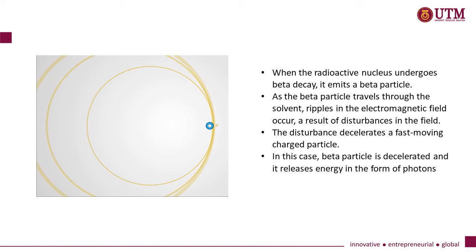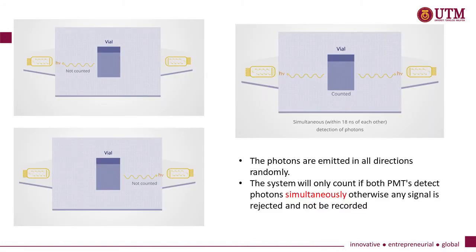The disturbance decelerates the fast-moving charged particle. In this case, the beta particle is decelerated and it releases energy in the form of photons. The photons are emitted in all directions randomly. The system will only count if both PMTs detect photons simultaneously; otherwise any signal is rejected and not recorded.